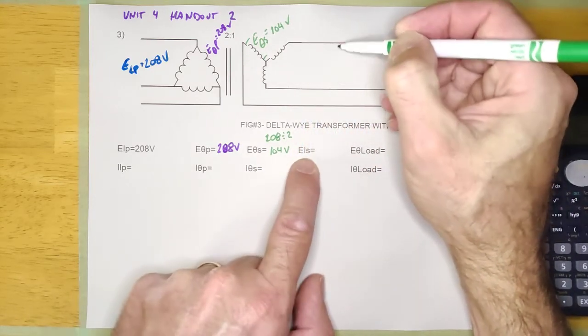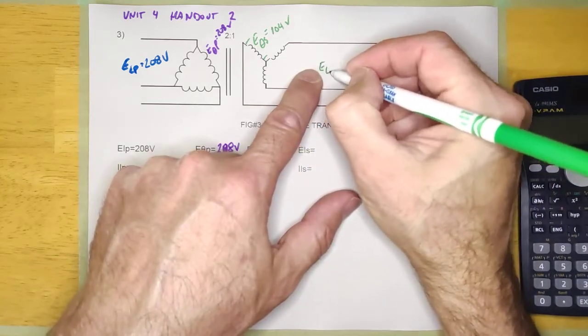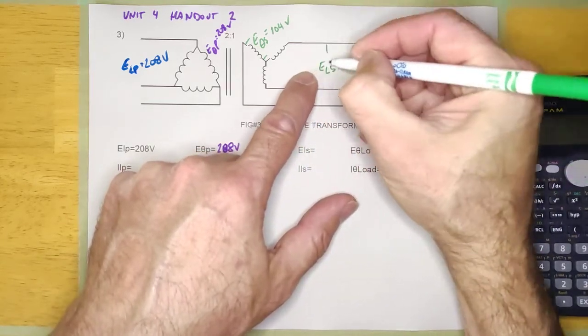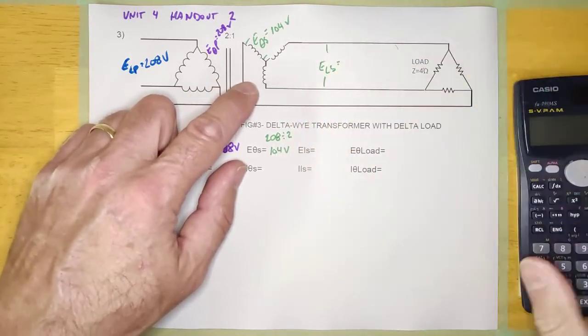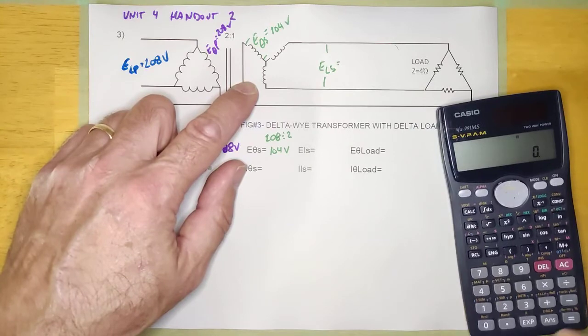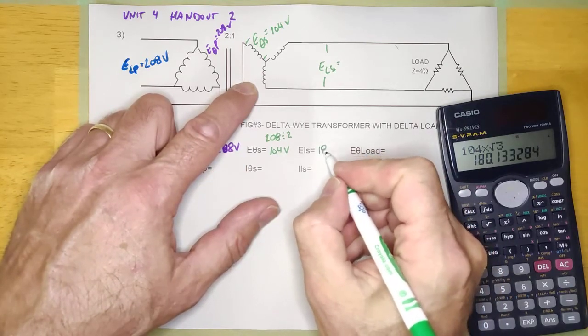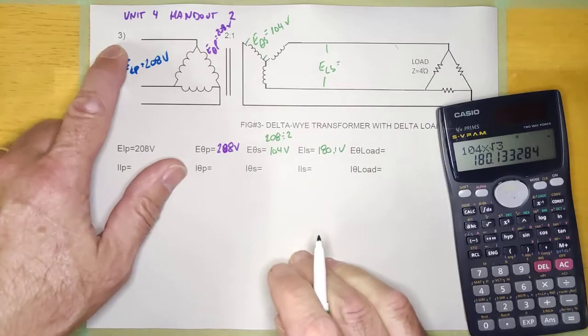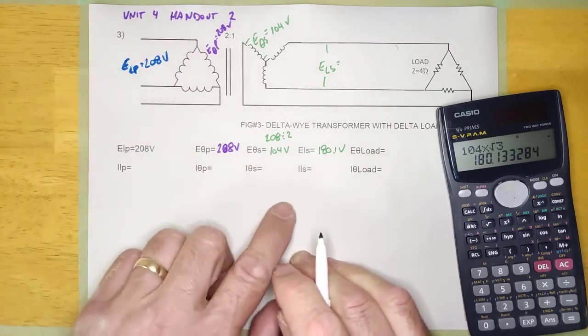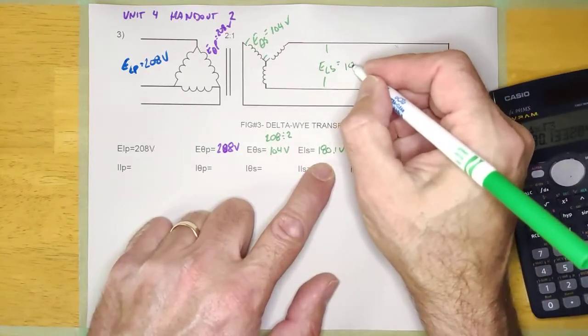So I've got 104 volts on each phase of the secondary. The question is, what is E-line secondary? Well, it's going to be greater — 104 plus that 104 — so it's going to be 104 times root 3. That gives us 180.1 volts. By the way, this is question number 3 from that handout — questions 1 and 2 I'll let you do on your own. So we've got 180 volts on the secondary line.